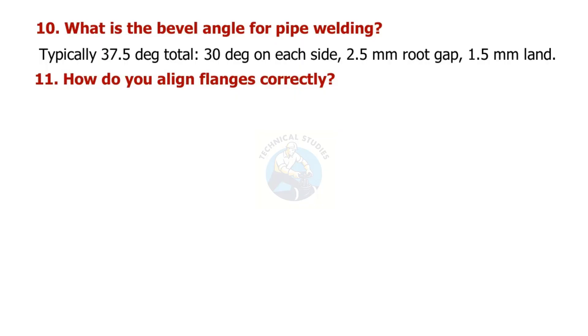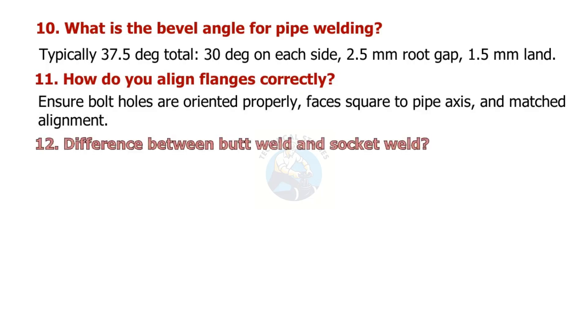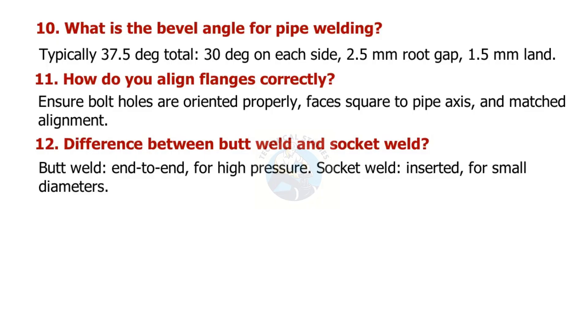How do you align flanges correctly? Ensure bolt holes are oriented properly, faces are square to the pipe axis, and matched alignment. What is the difference between butt weld and socket weld? Butt weld is end-to-end for high pressure. Socket weld is inserted and used for small diameters.